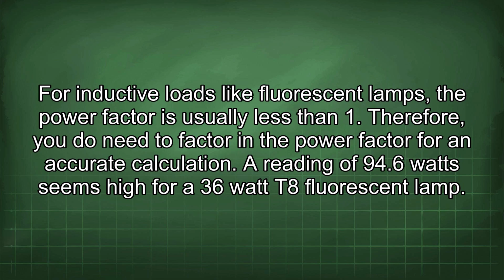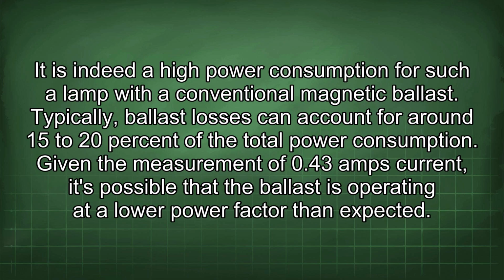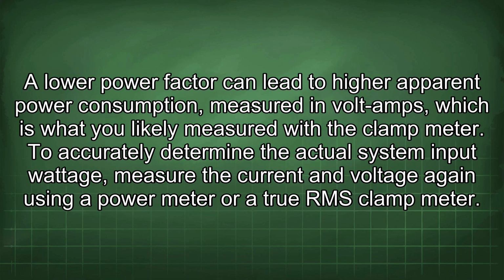A reading of 94.6 watts seems high for a 36 watt T8 fluorescent lamp. It is indeed a high power consumption for such a lamp with a conventional magnetic ballast. Typically, ballast losses can account for around 15 to 20% of the total power consumption. Even with the measurement of 0.43 amps current, it's possible that the ballast is operating at a lower power factor than expected. A lower power factor can lead to higher apparent power consumption, measured in voltamps, which is what you likely measured with a clamp meter.